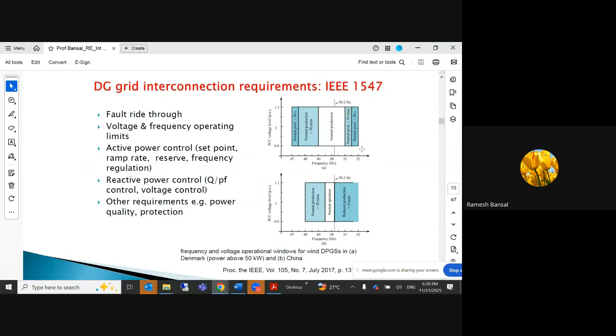They can help. For example, previously these photovoltaic systems' converters would operate at unity power factor. But now converters can operate on leading and lagging power factor, meaning they can contribute reactive power. They provide reactive power support, and by doing so, they can improve the voltage. When there is a fault, the voltage will go down, so they can help in recovering the fault condition.